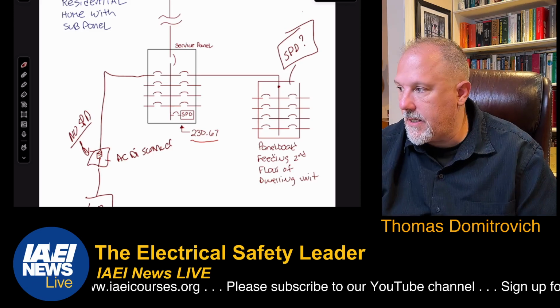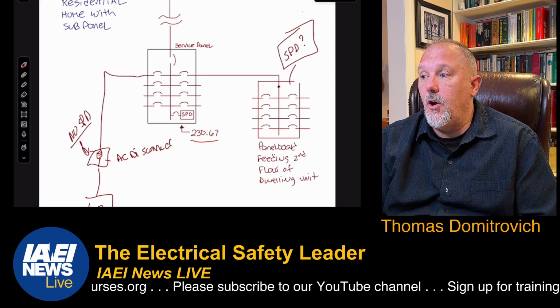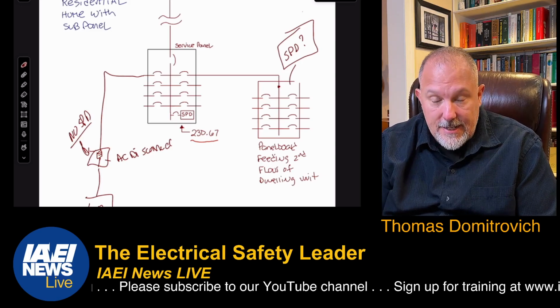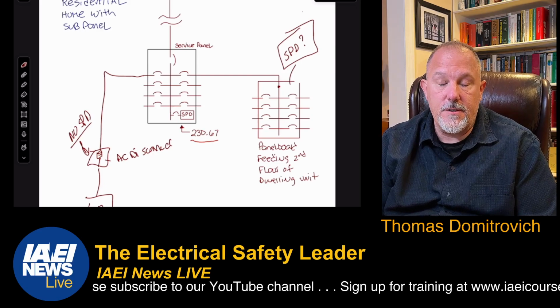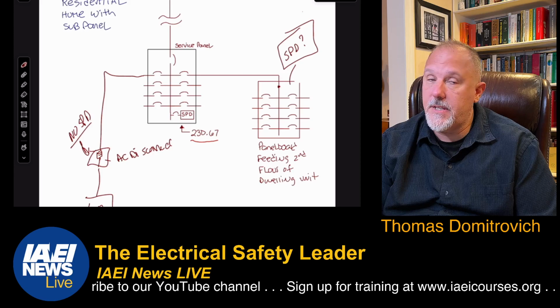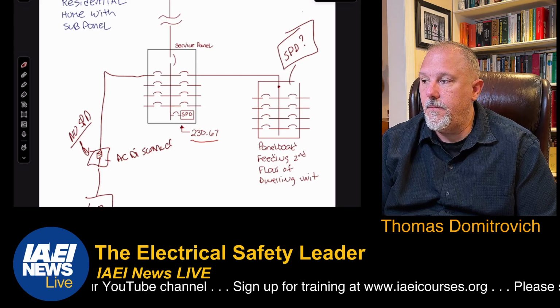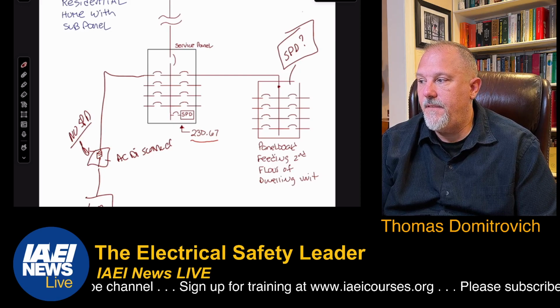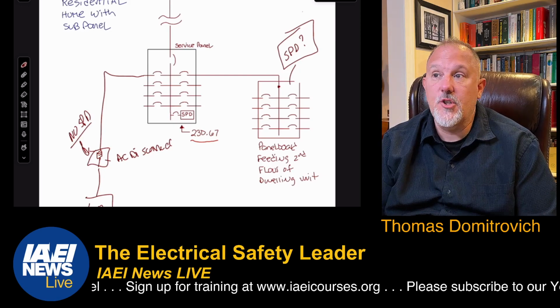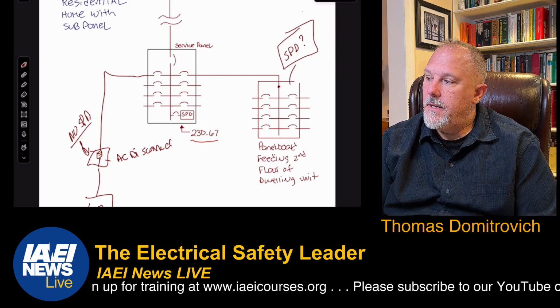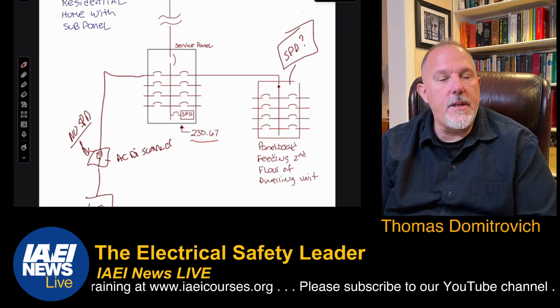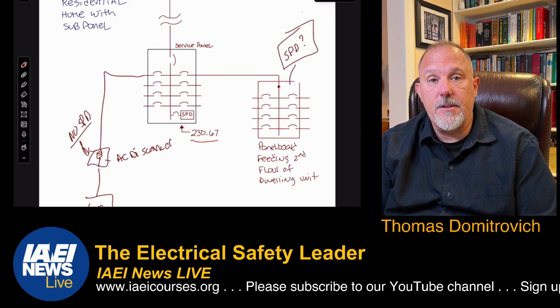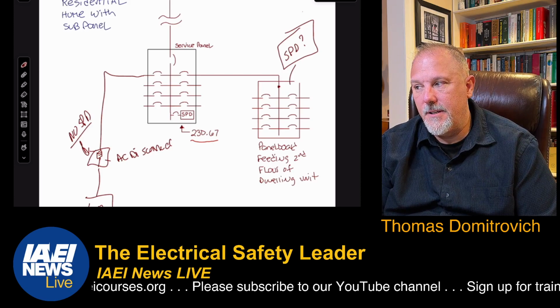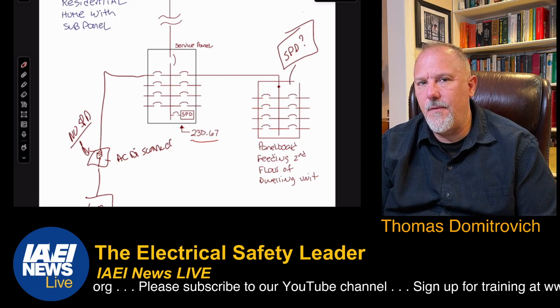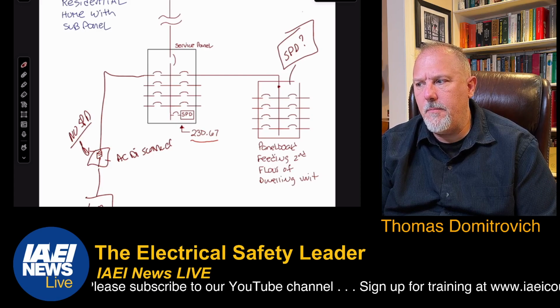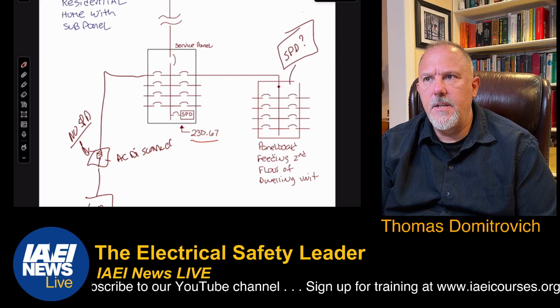That wouldn't quite be realistic, because it's not the overcurrent protective device that dictates whether or not you're going to have surge events. The goal of, and this is my opinion, the goal of 215 was to hit a feeder that supplies a dwelling unit or a dormitory unit, etc. And that panel board, if it serves the entire dwelling unit, then it would be covered, but it doesn't cover the entire dwelling unit. This is where the gray area is. If you can feel me on that one, I think we might need some clarity in 215.18.